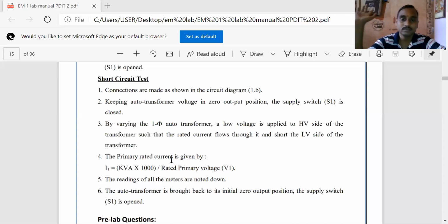You observe the current reading and vary the variac up to 8.6 ampere. Then note down all the readings. When the 8.6 ampere current reading is obtained, the corresponding voltage will be nearly 30 volt. Also note the wattmeter reading; you will get nearly 105 watts or 150 watts, etc. You observe all the readings of the meters, and the auto transformer is brought back to the original zero position, and switch off the supply. So this is the procedure for the short circuit test.